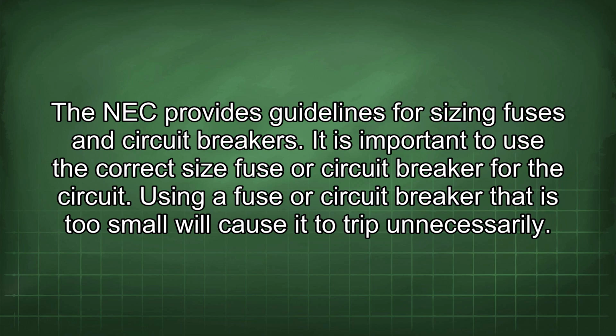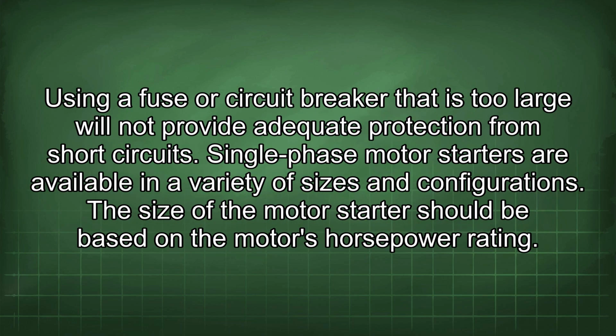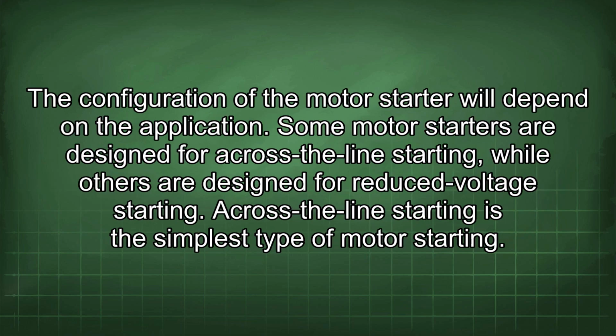It is important to use the correct size fuse or circuit breaker for the circuit. Using a fuse or circuit breaker that is too small will cause it to trip unnecessarily. Using one that is too large will not provide adequate protection from short circuits. Single-phase motor starters are available in a variety of sizes and configurations. The size of the motor starter should be based on the motor's horsepower rating. The configuration of the motor starter will depend on the application.